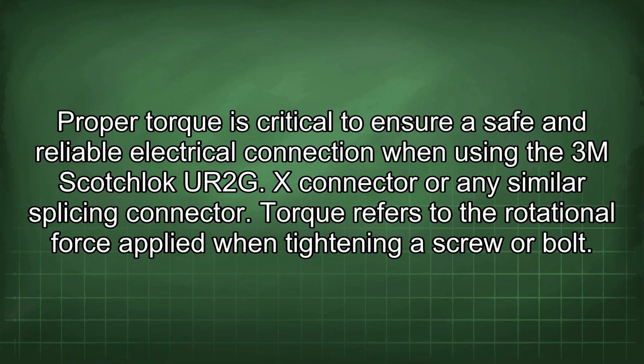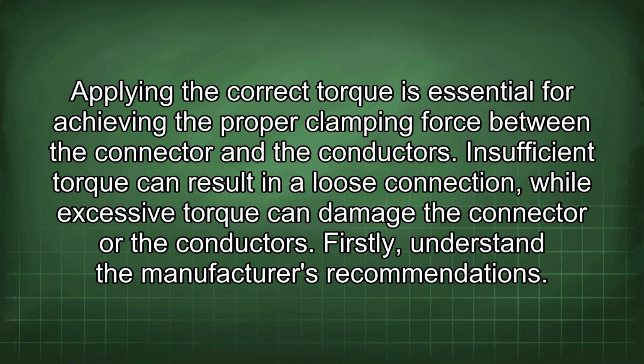Proper torque is critical to ensure a safe and reliable electrical connection when using the 3M Scotchlok UR2G X connector or any similar splicing connector. Torque refers to the rotational force applied when tightening a screw or bolt. Applying the correct torque is essential for achieving the proper clamping force between the connector and the conductors. Insufficient torque can result in a loose connection, while excessive torque can damage the connector or the conductors.